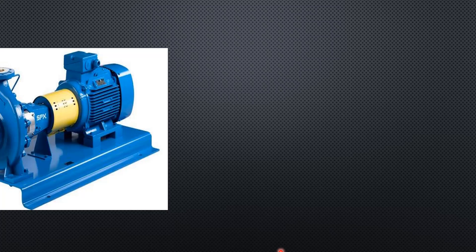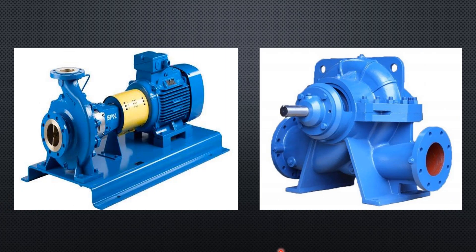The third parameter is the pump nozzle arrangement. Comparing two photos: one pump has a front entry and top discharge, while another has a side entry and side discharge. Only when you know the nozzle arrangement can you plan the piping correctly. You cannot simply copy the piping of one pump to another, because nozzle arrangements vary with pump type and manufacturer. Don't forget to evaluate the nozzle arrangements.